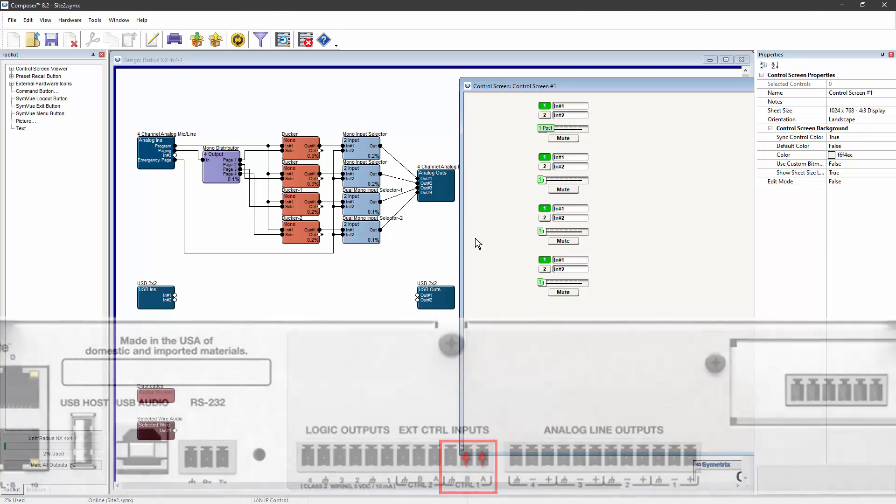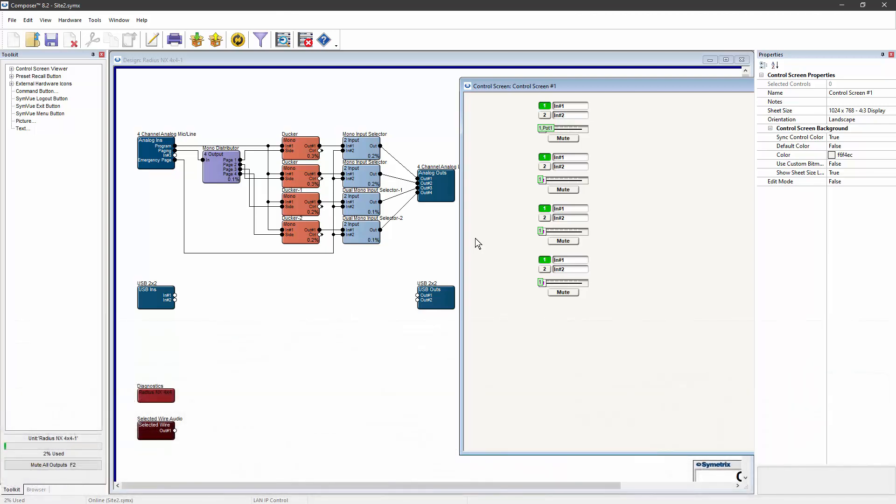It's important to remember that when contacts A and B are shorted, the input selectors will switch to input number two. So in this example, I'm using input one as my normal program and input two as my emergency page. That works fine as long as I have a normally open connection from the fire system. In most cases, it's actually better to have a normally closed connection from the fire system. And in that case, you just use input number two as your normal input and input number one as your emergency paging input.